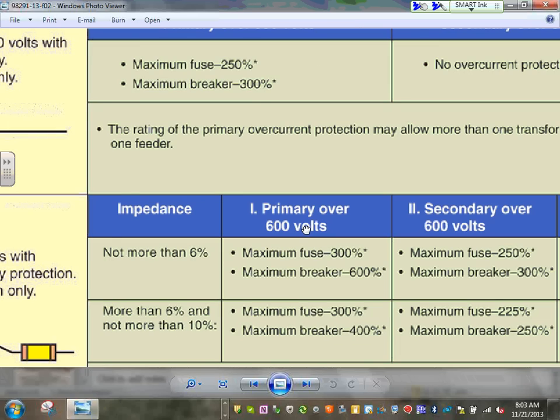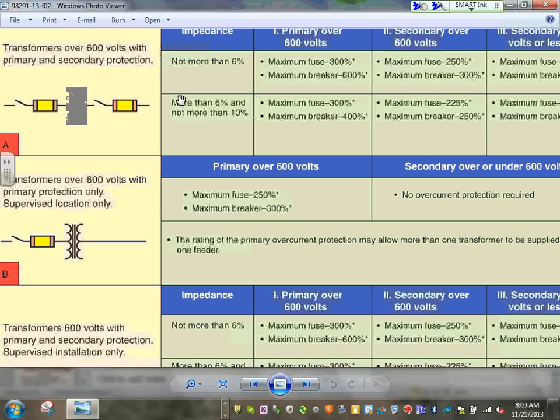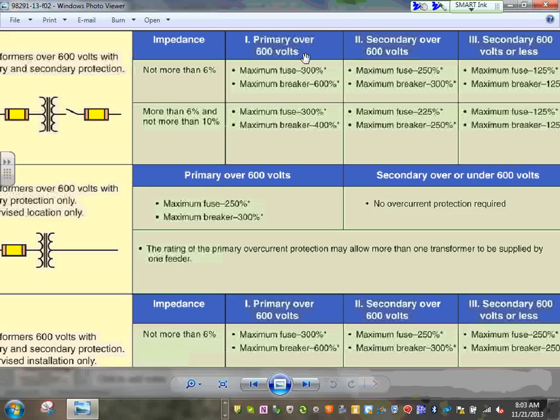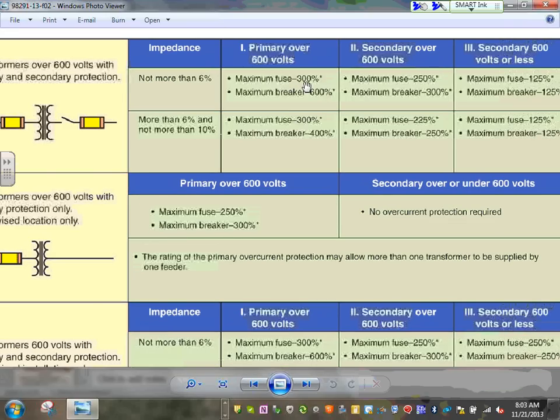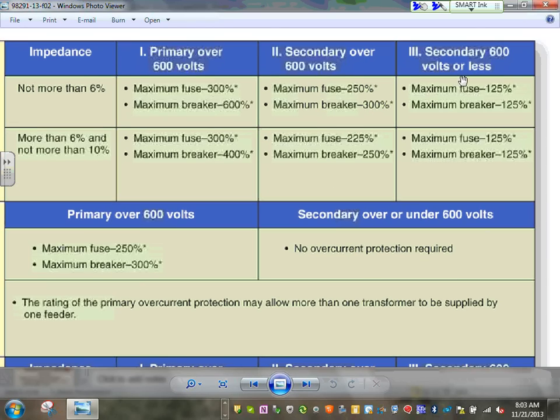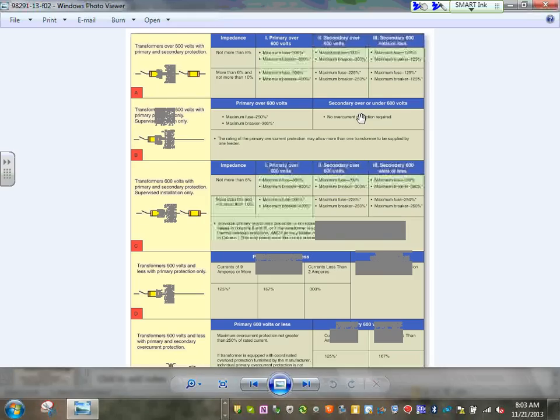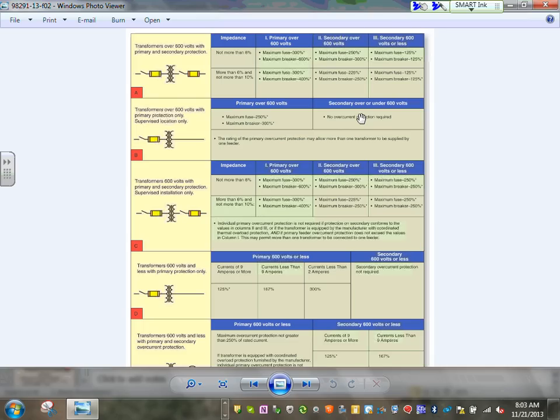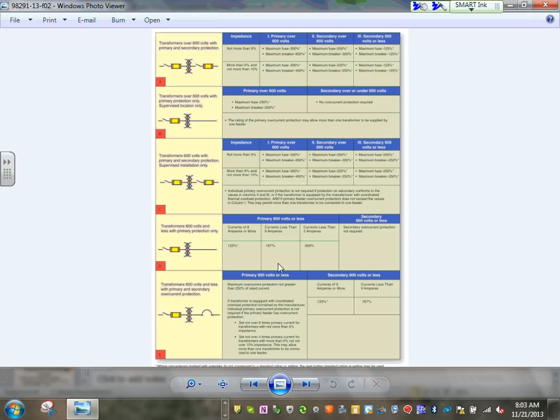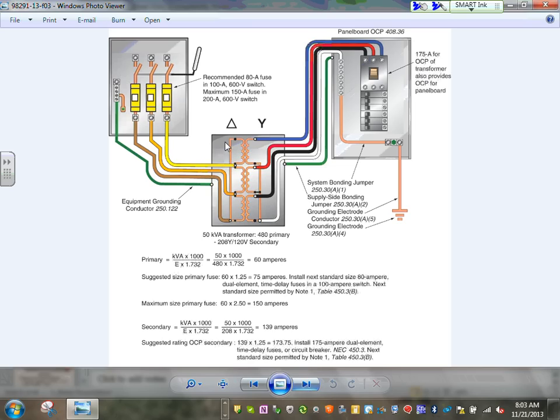I want to bring to your attention, guys, if you have a primary and secondary protection like this, for example, if the primary is over 600 volt, you're using 300% for a fuse, or a circuit breaker 600%. If the secondary is over 600, still, here's your multiplier. If your secondary is less than 600, here are your multipliers. Again, we will go over the whole calculation for this in the industrial, because that's when we have our transformer. So we'll dedicate more time to using this table on the industrial project. For the time being, I can't emphasize how important this table is. It's also coming in the NEC code book directly.